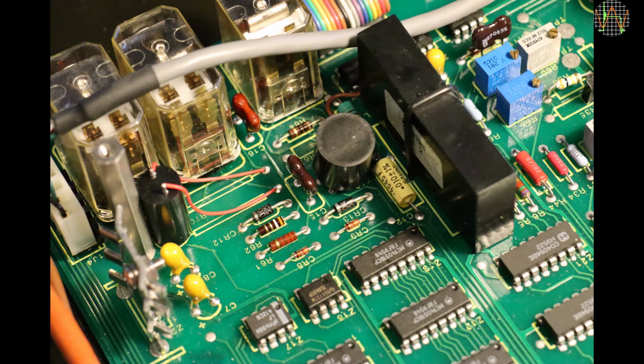In milliamp mode, the processor limits the maximum value you can enter, so the highest stack output is 1 volt, which translates to 100 milliamps.